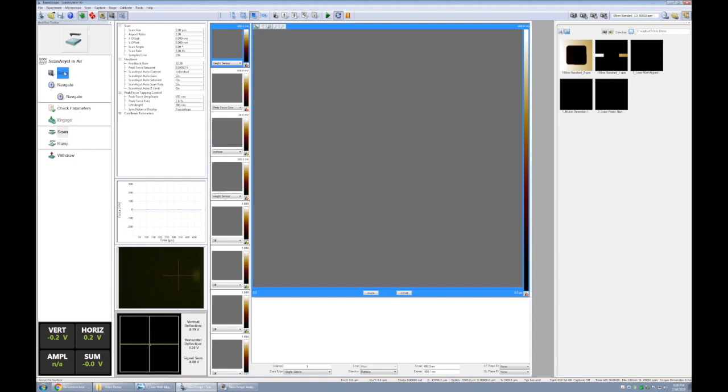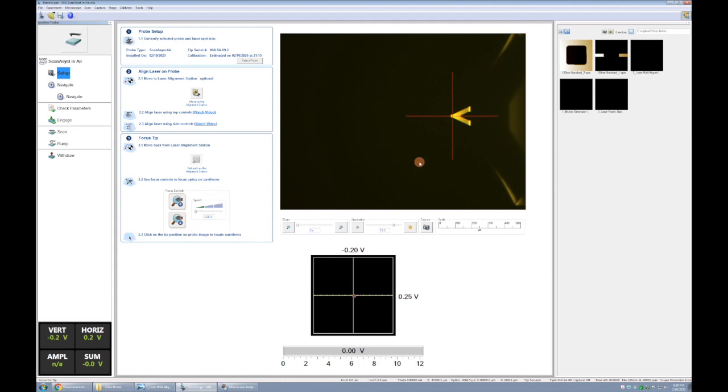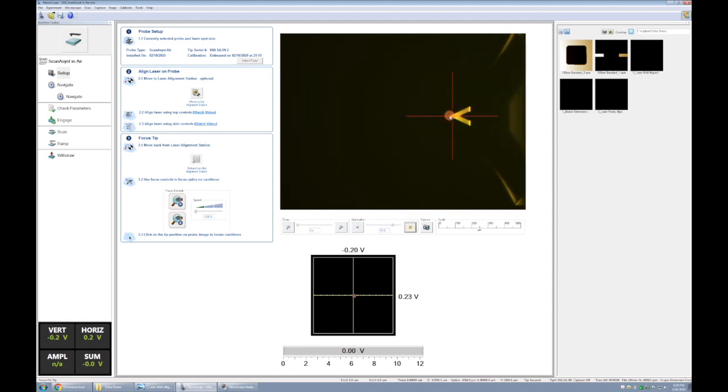So we'll begin with setup, and we'll do these in order. The first thing to do though is to confirm that our probe is properly loaded. So I don't have a video showing how to do all the loading of the probe, and loading the probe onto the scanner, and handling the scanner. You'll want to talk to lab staff about how to learn to do that safely. But once you do have the probe loaded into the scanner, we'll want to confirm that it's in the right position. So you can do that by zooming all the way out digitally, and choosing a good amount of illumination. And we want our probe to be about one quarter of the way in from the right side of the screen when we're fully digitally zoomed out.